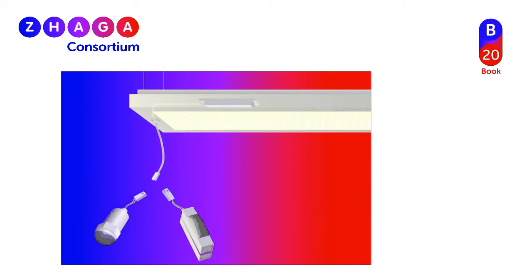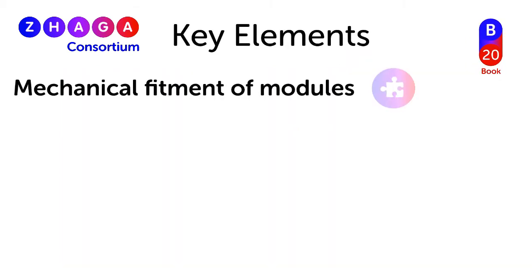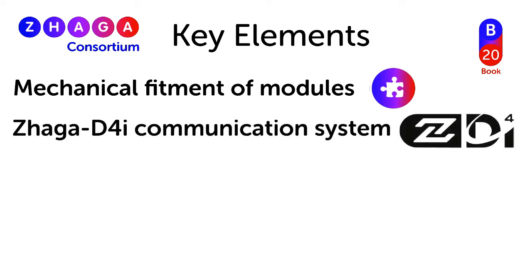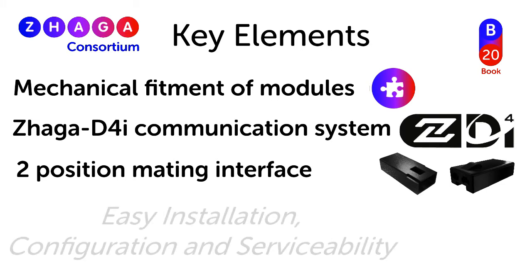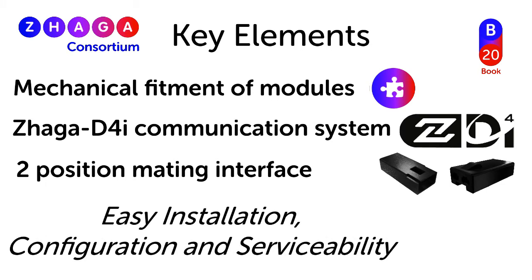Key elements of the Zhaga Book 20 standard include standardized mechanical fitment of modules to a luminaire, support of the D4i digital communication system and Zhaga-D4i certification, and the use of a standardized mating plug and receptacle for the modules. Book 20 permits easy module installation and field serviceability, allowing a non-technician to easily replace or upgrade a module without the use of any specialized equipment or tools.